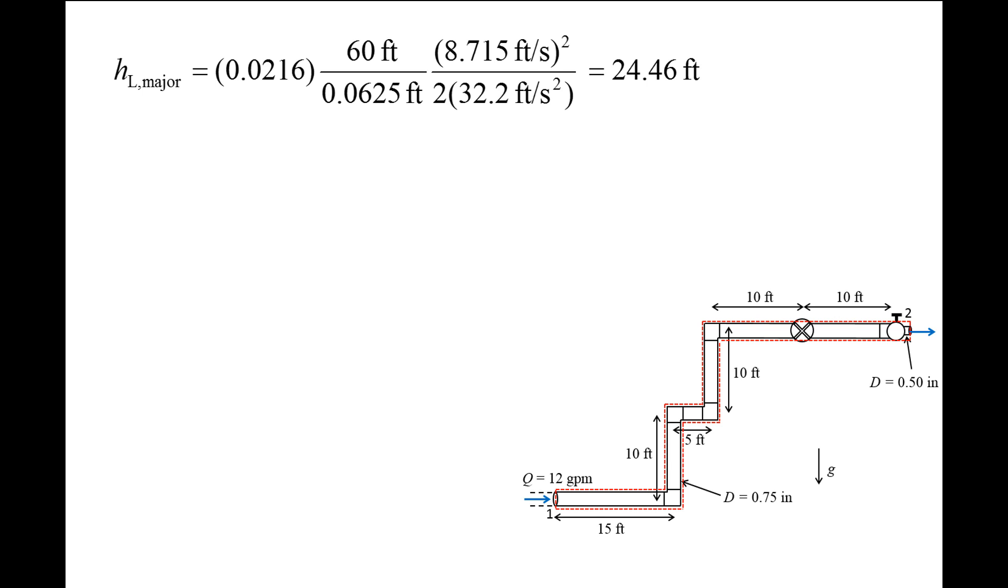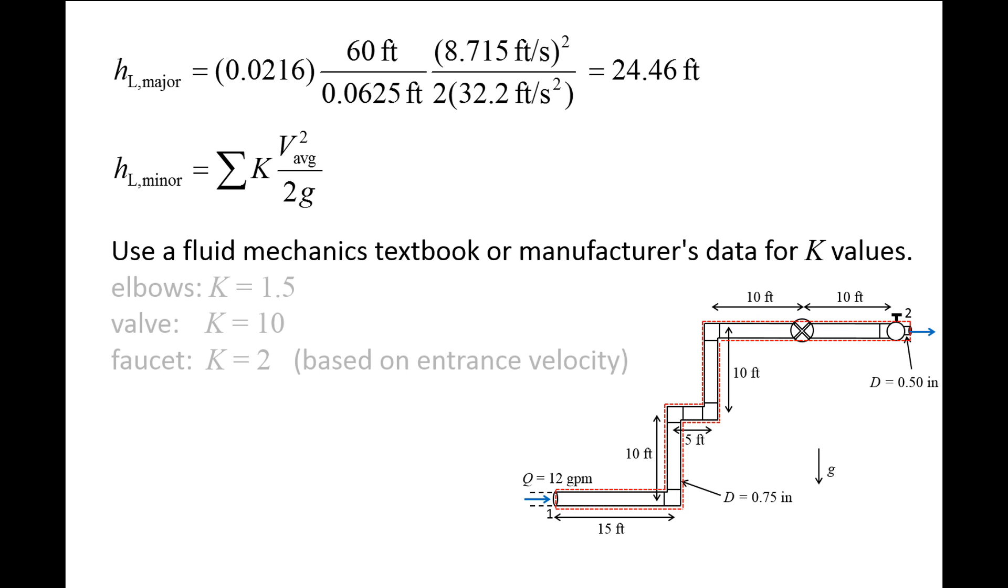Next, we turn our attention to finding the minor head loss. The equation for the total minor head loss is the sum of the minor head loss for each component, which is the loss coefficient K times the average flow speed squared over 2g. The values of the minor loss coefficients are dependent upon the particular design of the component. We can obtain estimates of loss coefficients from fluid mechanics textbooks or from the manufacturer of the components if they provide them.